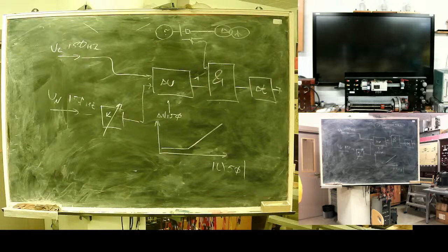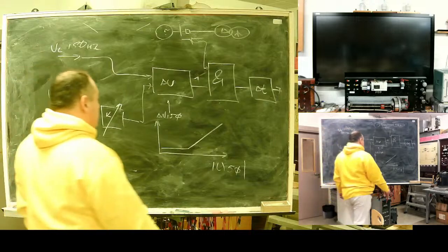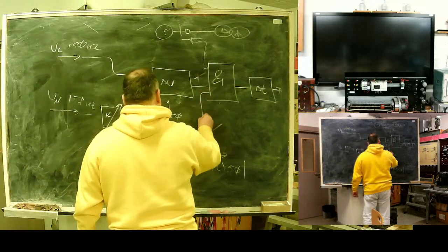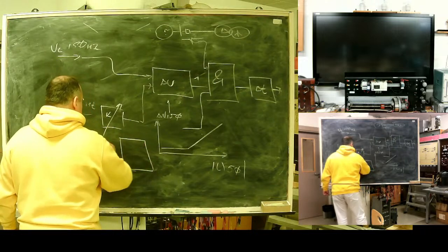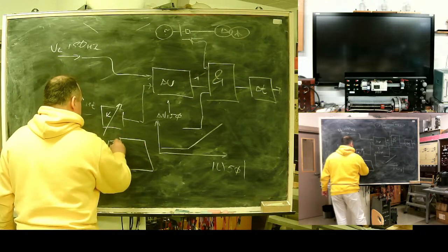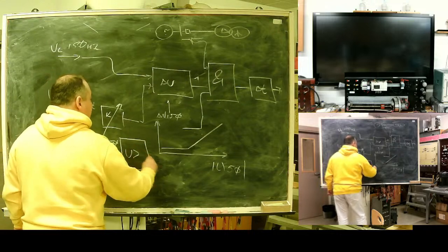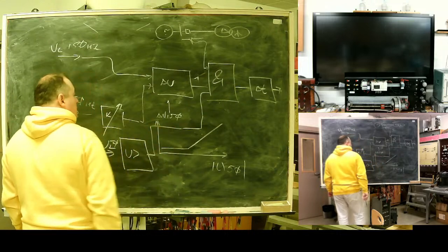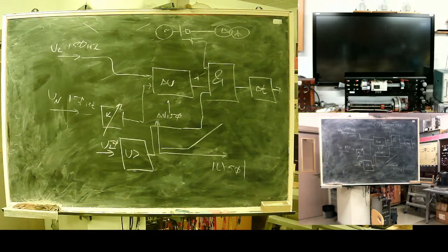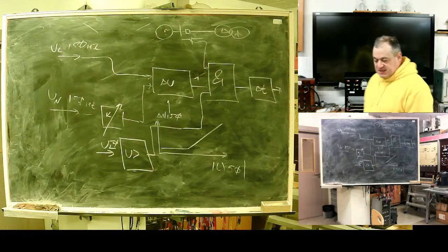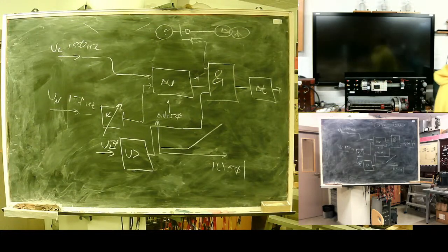So, to prevent misoperations, line at 50 Hertz, this protection should be disabled until the output generator voltage at 50 Hertz is at least 0.9, or it will misoperate.